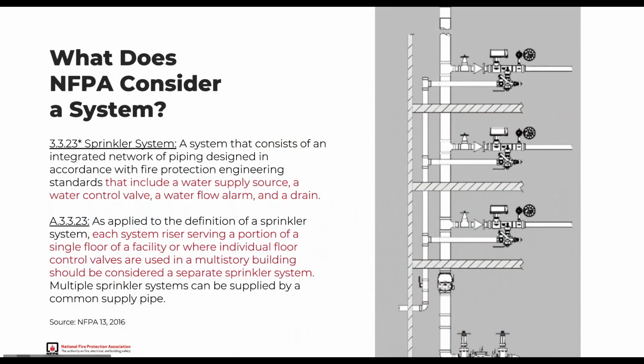And in addition to the changes in 2016, they also cleaned up the definition of a sprinkler system. For those who have multi-story buildings, the concern is that initially some people would say, well, I saw a backflow preventer and alarm valve, and I've got a 4 or 5 story building, that's one system. But now that you've got individual control valves and individual check valves on each and every floor, the definition of a system has been, to paraphrase it, that if you can control the water, sense flow of water, and drain the water, that's a system.